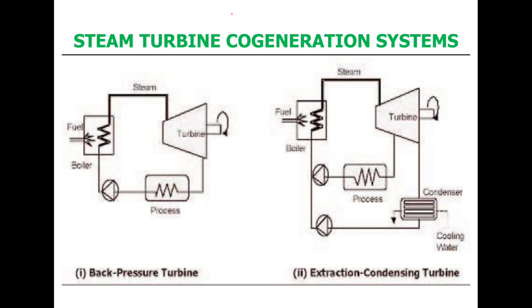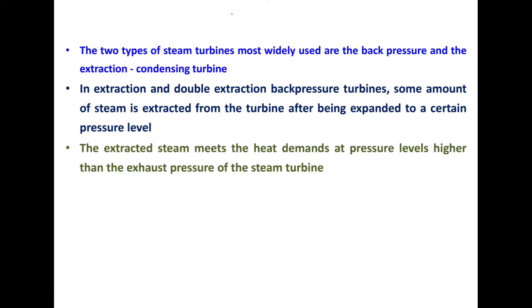In the extraction condensing turbine, the condenser unit is provided separately and the process unit is connected at the middle of the turbine stage. The exit steam enters the condenser, and then re-enters the boiler to generate steam, which is fed back into the turbine entry. The process unit is joined at an intermediate point between the turbine entry and exit. This is how the extraction condensing turbine works. The two types most widely used are the backpressure and the extraction condensing turbine.